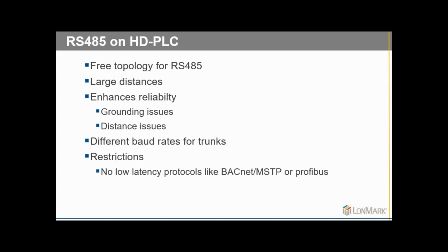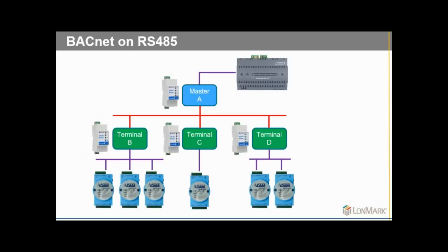You can implement free topology, long distances, and you can even do something pretty cool: different trunks can use different baud rates. If you are tunneling RS-485 on something like Ethernet, it's dependent on the gateway letting out the RS-485 again, which baud rate you have. So even if all of the devices talk with each other - I made the SmartServer IoT from Adesto the master - the different trunks can have different baud rates. You never can do that with a standard Modbus installation. So yet another trick to solve some problems.